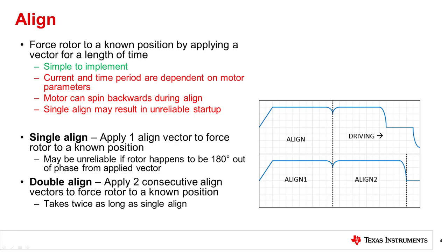Lastly, there is a small chance that the rotor happens to be 180 degrees out of phase from the Align vector, in which case the rotor will fail to align properly. One way to mitigate this potential downside is to use Double Align and apply two consecutive yet different Align vectors to ensure that the rotor will align to at least one of the applied vectors. Of course, the consequence of applying two Align vectors is that Double Align will take twice the time to complete compared to Single Align.